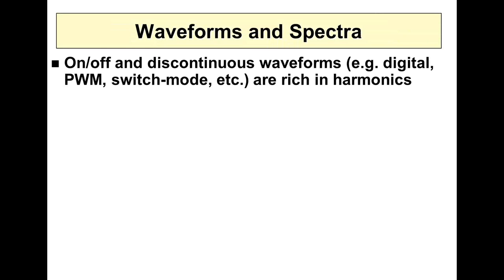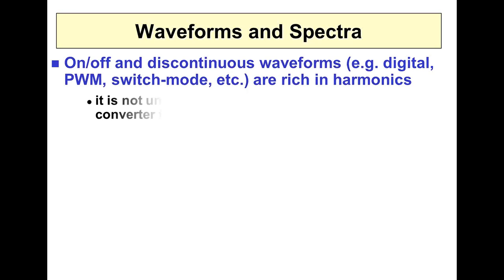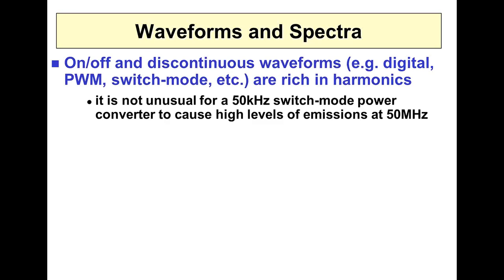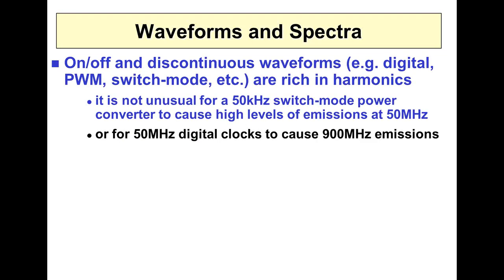When you do EMC, it helps if you get used to thinking of things as seen on an oscilloscope and also on a spectrum analyzer at the same time. Swapping between domains helps you understand what's going on. These days we're using an awful lot of discontinuous waveforms — like digital waveforms, switch mode power converters, and pulse width modulation. These waveforms, when analyzed on a spectrum analyzer, are very rich in harmonics. It's not unusual for 50 kHz switchers to give high emission levels at over 1,000 times the switching frequency — that's the 1,000th harmonic — or for 50 MHz digital clocks to cause emissions at more than 900 MHz.